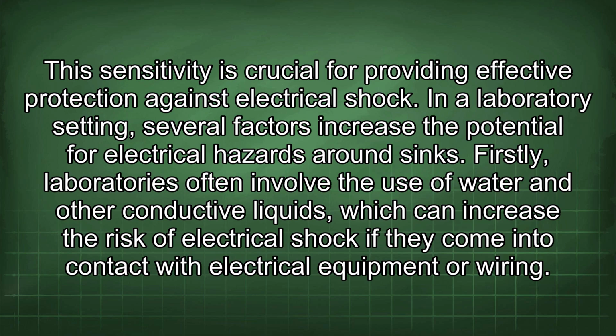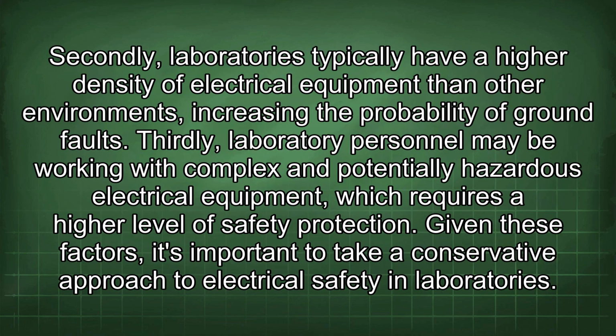In a laboratory setting, several factors increase the potential for electrical hazards around sinks. Firstly, laboratories often involve the use of water and other conductive liquids, which can increase the risk of electrical shock if they come into contact with electrical equipment or wiring. Secondly, laboratories typically have a higher density of electrical equipment than other environments, increasing the probability of ground faults. Thirdly, laboratory personnel may be working with complex and potentially hazardous electrical equipment, which requires a higher level of safety protection. Given these factors, it's important to take a conservative approach to electrical safety in laboratories.